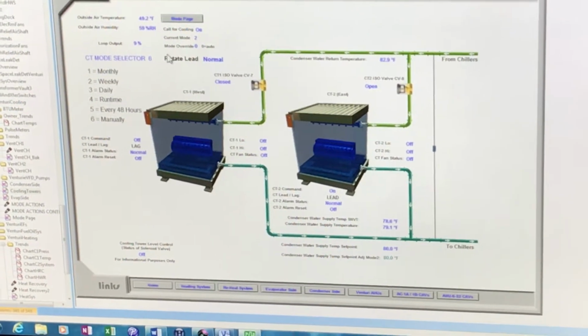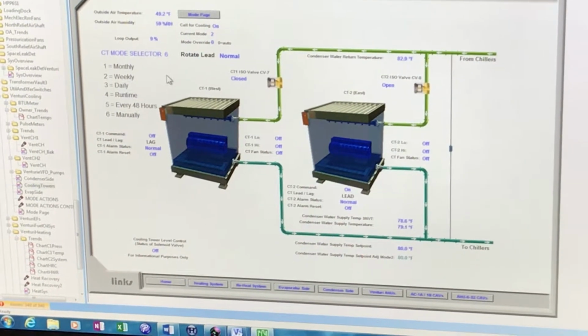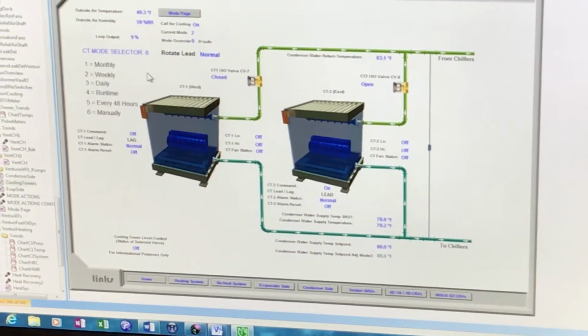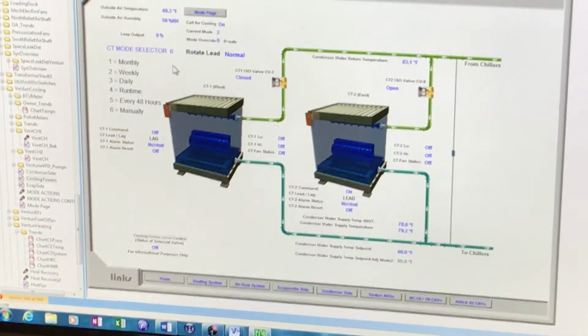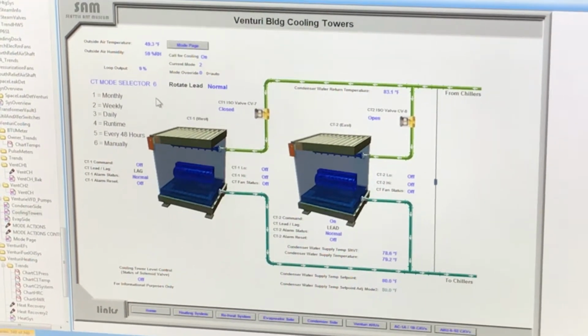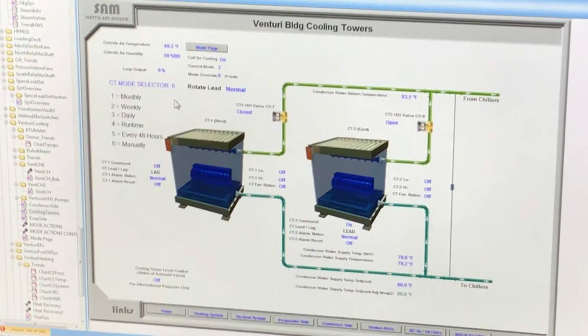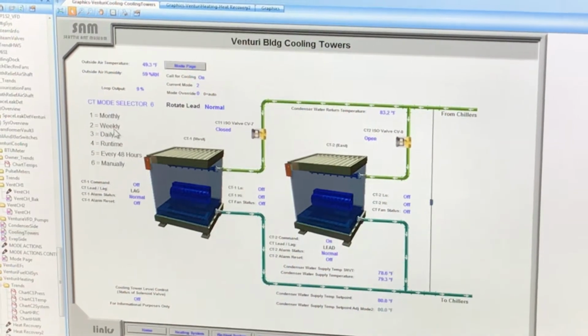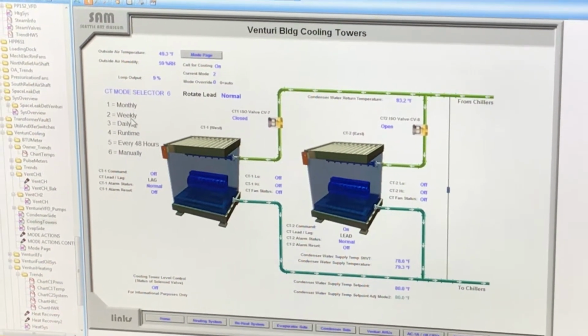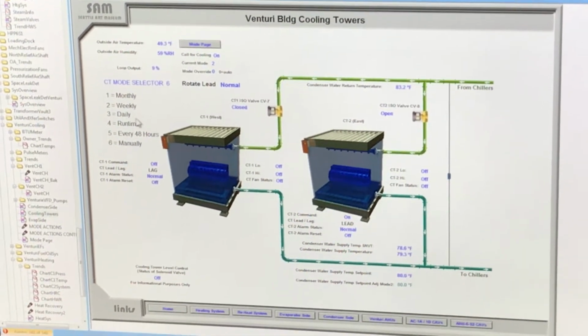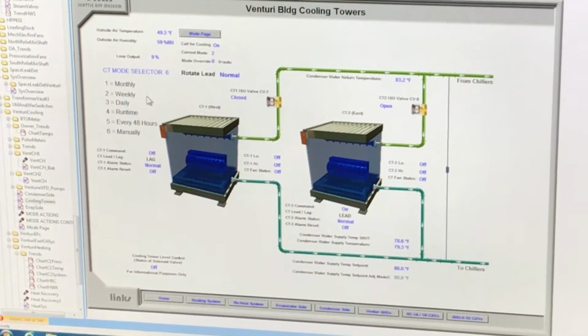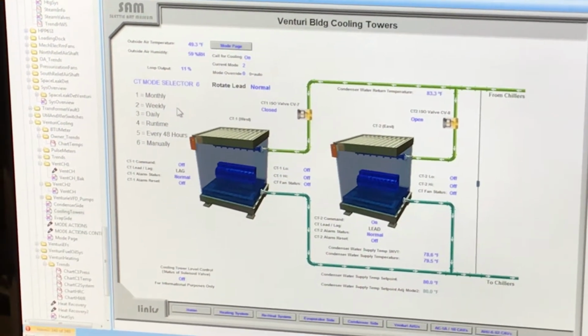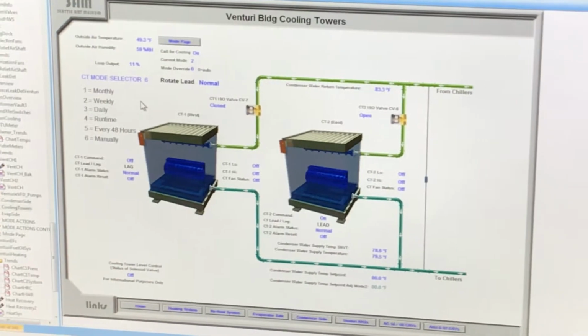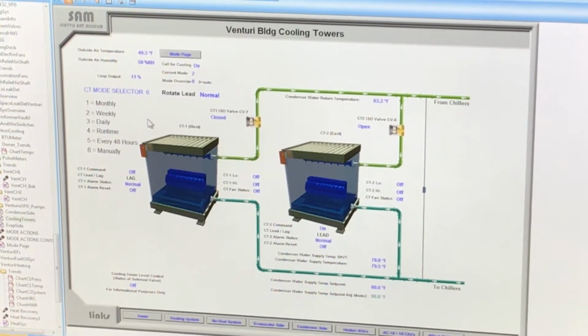So why would you have monthly, weekly, and daily? It depends on how we want to rotate them. There's probably a generic monthly date, like the 1st or something like that, and the same with the weekly, every Sunday. So that's just a change of which one is going to run as the lead. That's correct. That way we don't put all the stress on one cooling tower all the time.